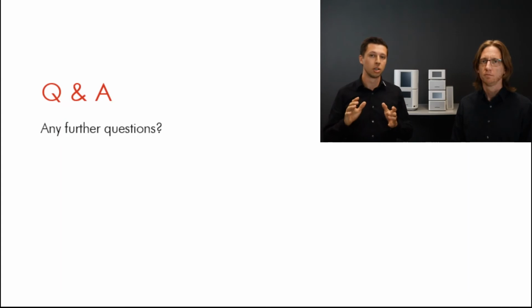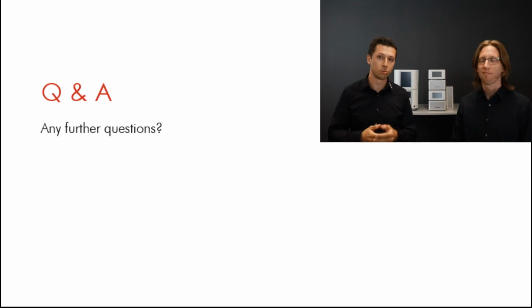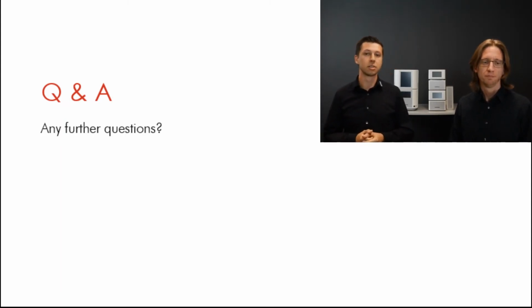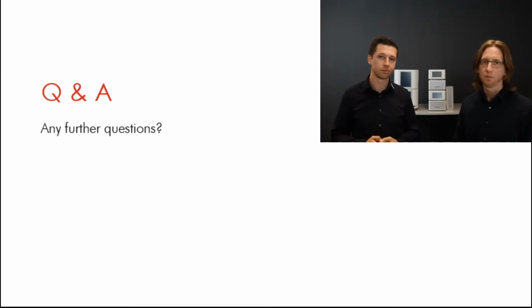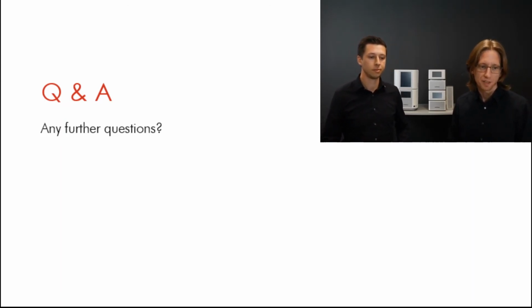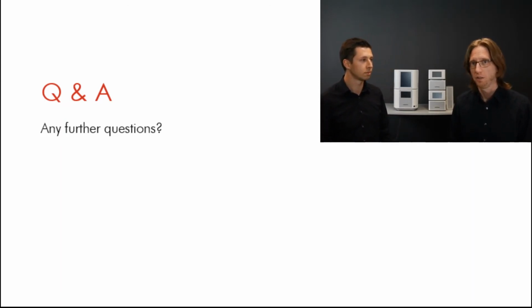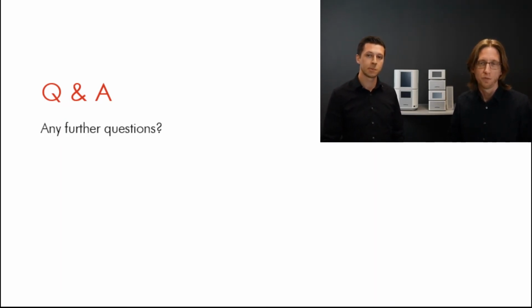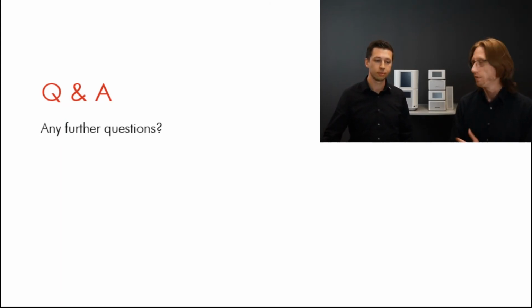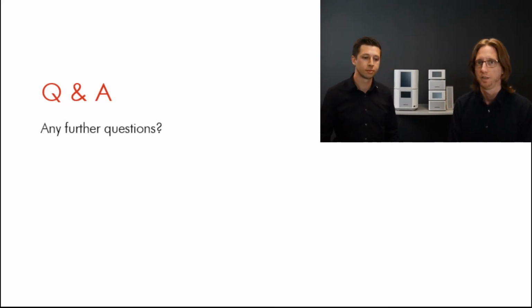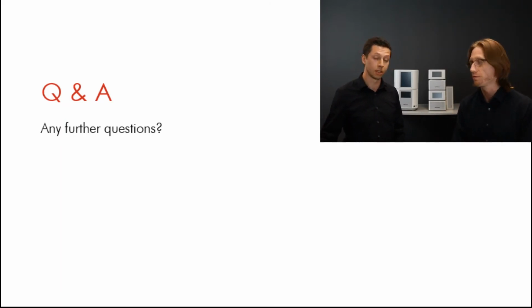So usually don't touch the advanced calibration, check it with us if there's any other possibility or solution for this, and then we can have a look, for example, for the advanced calibration. But usually there's at the beginning no need to change the advanced calibration. Yeah, that is correct. And I would like to add that the advanced calibration is also done on the remote maintenance every year. So this will be checked by us together with the customer during the remote maintenance. So as Robin mentioned, we shouldn't touch it until we figure out that this must be the root cause for this problem.